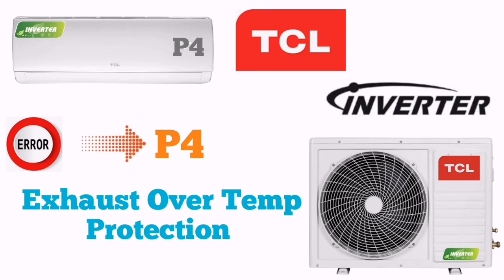When you see error P4, it means exhaust over temperature protection in our outdoor unit. First of all, you have to check the inlet airflow and outlet airflow of our outdoor unit, if it is clear or not. If it is not clear, make it clear, and your unit will be working.